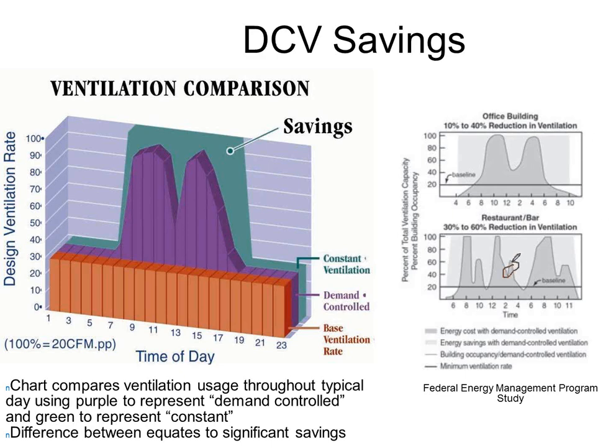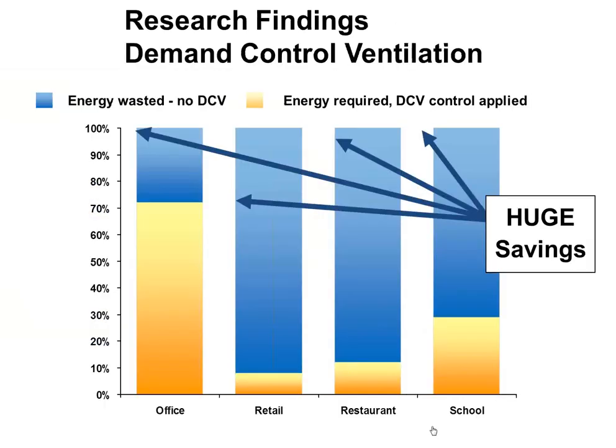So after lunch, you got these people that come in and go to lunch at 1, 2 o'clock in the afternoon or whatever, right? When you're at lunch in the daytime over here in the big V, somebody else is at the office, and then you kind of flip-flop. So that happens. The point is that these patterns for different building types, school, office, restaurant, etc., are very predictable for buildings, and hence because they're predictable, we can easily give people a good guesstimate of how much energy can be saved on a given project if we know what kind of building they have.